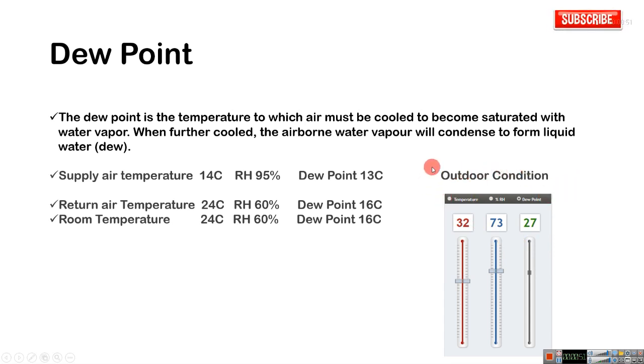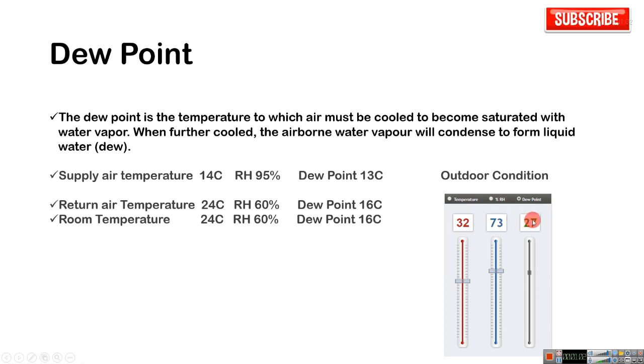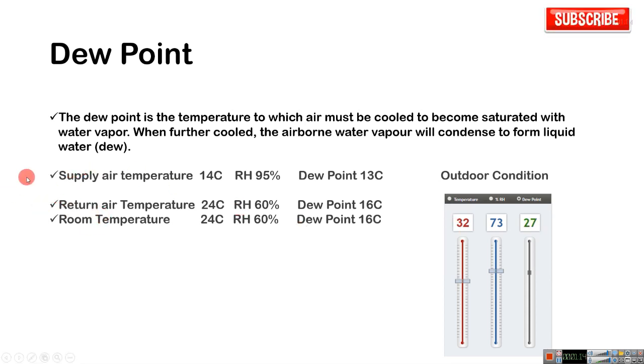Look at this outdoor air condition example. The dew point temperature: outdoor temperature is 32°C, relative humidity is 73%, and the dew point is 27°C. If this air is cooled below 27°C, there will be condensation. Think about the supply air at a temperature of 14°C and RH 95% — the dew point temperature is 13°C.